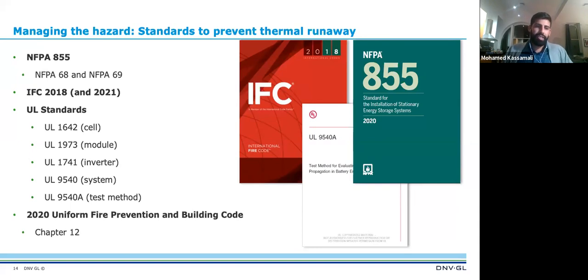Now these last two are more nuanced certifications or testing protocols. UL 9540 is a field evaluation or certification process for your entire system, involving the inverter, the battery, and other system components. Essentially what UL is trying to do is assess the interoperability of those systems to make sure they're firing on all cylinders, communications are happening, power conversion is happening, and proper discharge and charging is occurring. All of that is assessed in 9540, but it's also assessing key safety features such as thermal management and venting of off gases, which leads into UL 9540A testing.